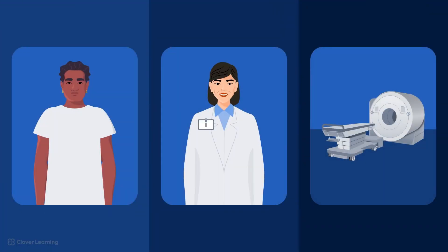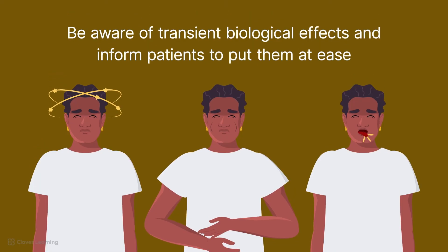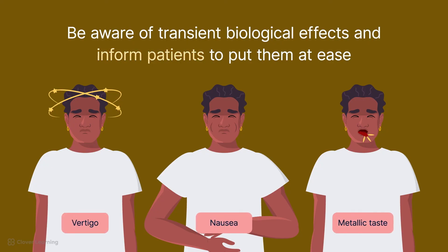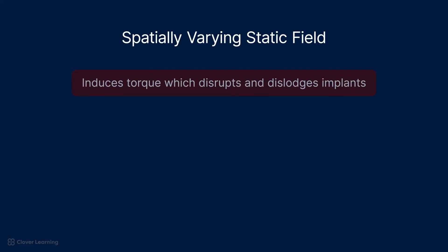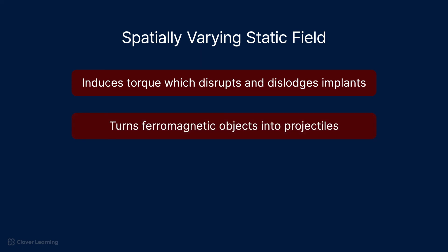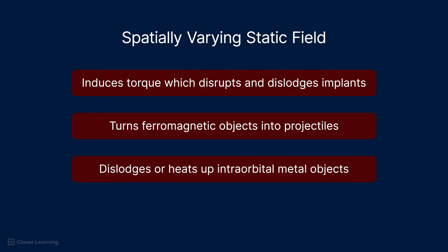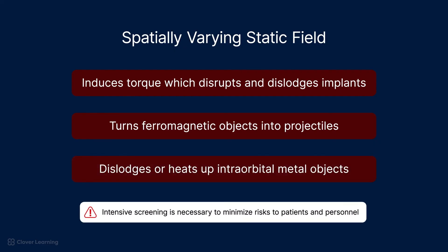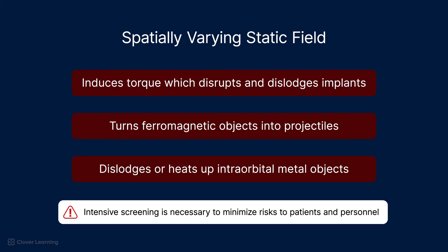In summary, the spatially varying static field in MRI presents a number of specific safety issues to both patients, MRI personnel, and the MRI scanner itself. It is important to be aware of the transient biological effects such as vertigo, nausea, or a metallic taste and inform patients to put them at ease. The spatially varying static field can also induce torque which disrupts and dislodges medical implants, turns ferromagnetic objects into projectiles, and can dislodge or heat up intraorbital metal objects. Intensive screening is necessary to minimize these risks to both patients and personnel.